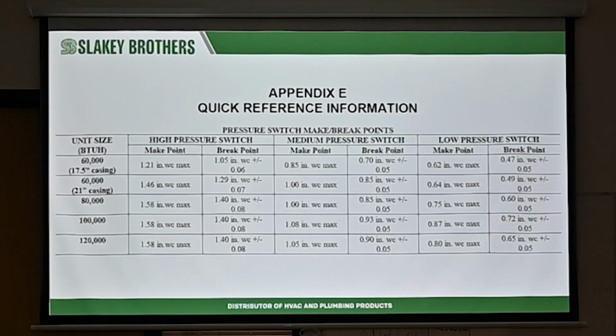This is only because it's a service manual. If you look at your service manual on the back of your 987, if you can't read the numbers on the pressure switch on the modulating furnace, this actually tells you your break point and your make point. You can kind of see the difference in the BTUs on what they make and what they break at. But either way, for your high pressure switch, medium pressure switch, low pressure switch, you still see the difference is 0.15. So I would say between 0.15 to 0.2 above that PF level, that switch needs to close.